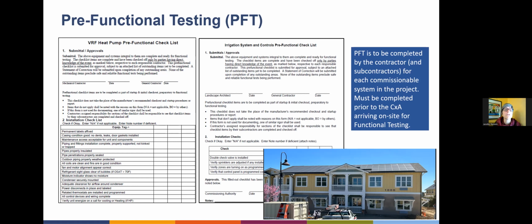falls under needing commissioning. So there's a pre-functional checklist for the variable refrigerant heat pumps. And some of this stuff can include really simple things like, for example, are the air filters installed? So you don't want your commissioning agent to come out there if the folks haven't got the pipe insulation on the pipes yet, or if there's kinks in the piping, or if those air filters aren't there, or if they haven't gone through and verified some of the other systems that are up and operational.